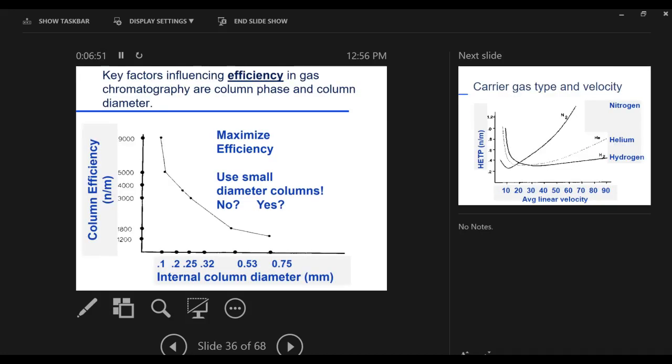This is a formula that kind of puts the factors together that influence our resolution, our ability to separate. I'll mention just a little bit about these different factors and say what we can do about them. Key factors influencing efficiency. How do we make our column more efficient, our separation better? A very important factor in column efficiency is the size of the column we're using. This is the internal diameter in millimeters: 0.1 millimeter, 0.2, 0.3.